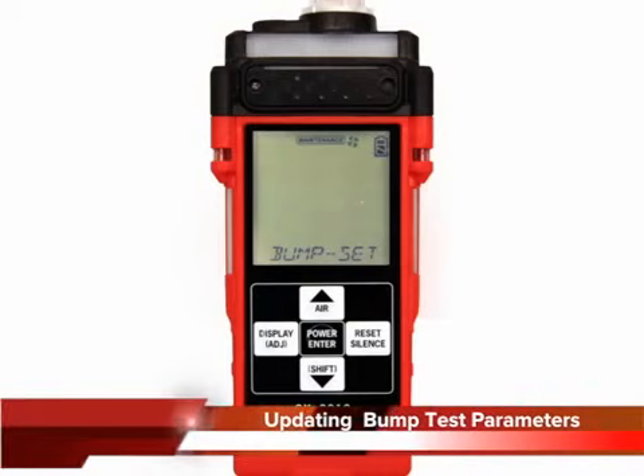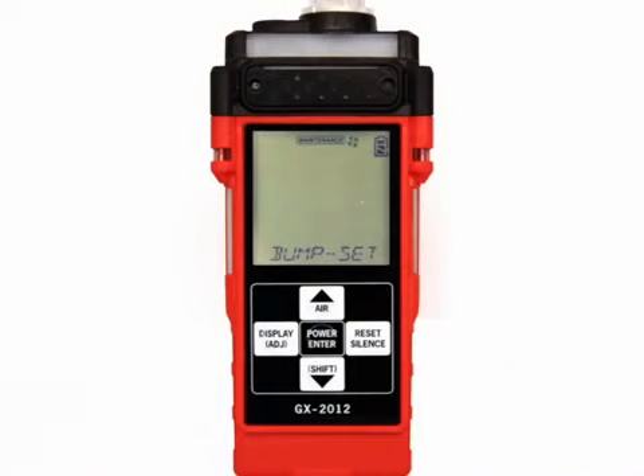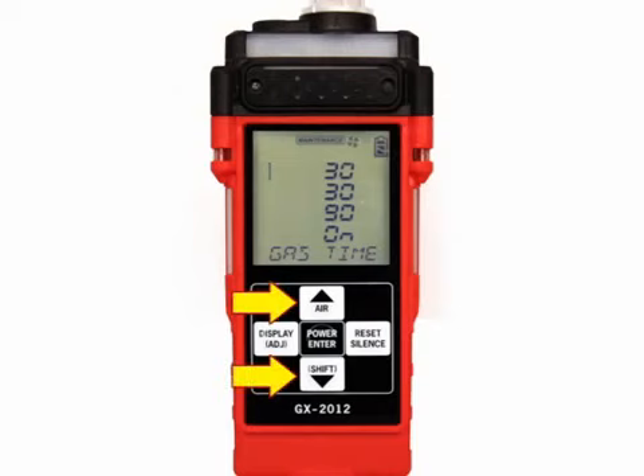The Bump Set menu item is used to adjust the bump test parameters. Use the Air or Shift buttons to display the Bump Set menu item. Press and release the Power Enter button. The values displayed are for gas time, check, bump test tolerance, cal time, and AutoCal. The cursor on the left of the screen shows which setting is associated with the parameter shown at the bottom of the screen. Use the Air or Shift buttons to scroll up or down along the list.